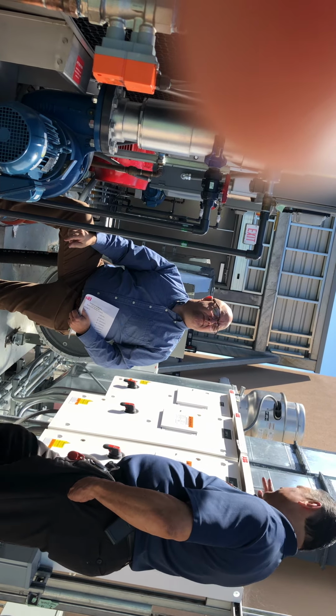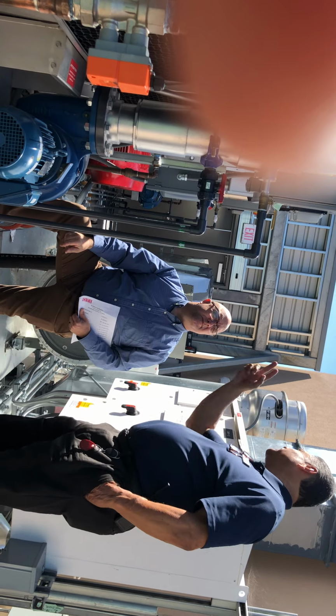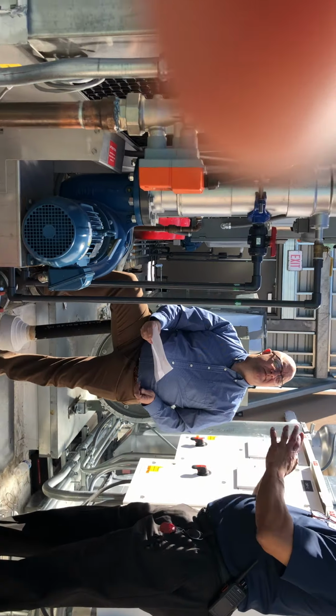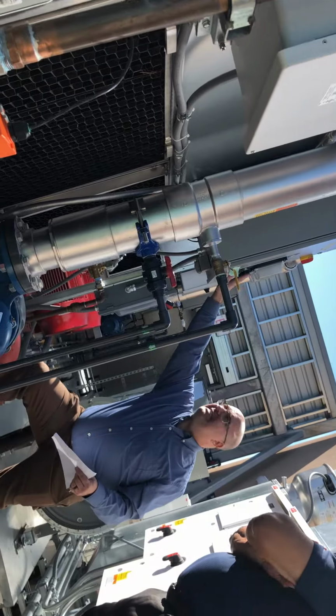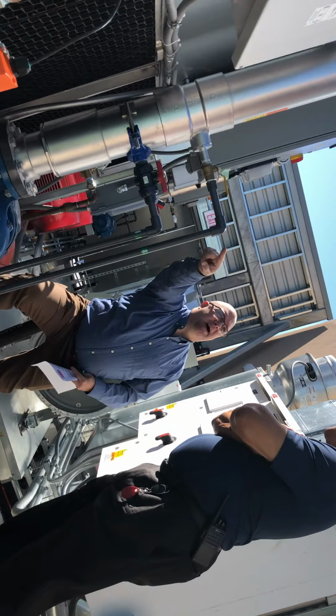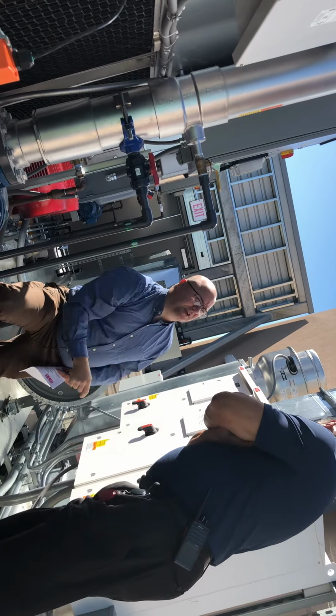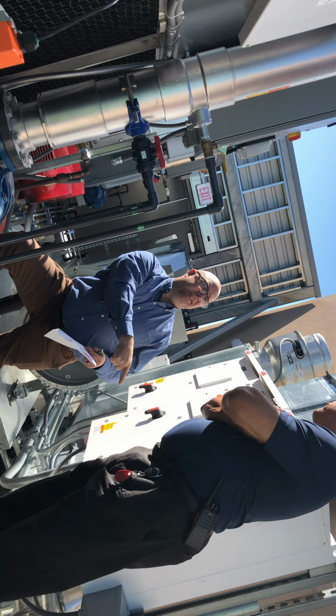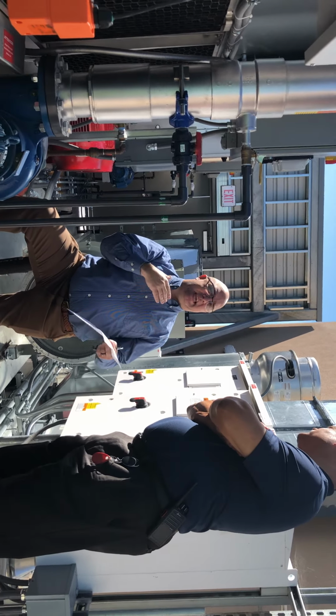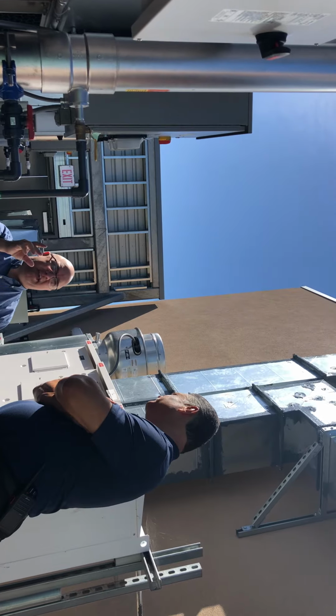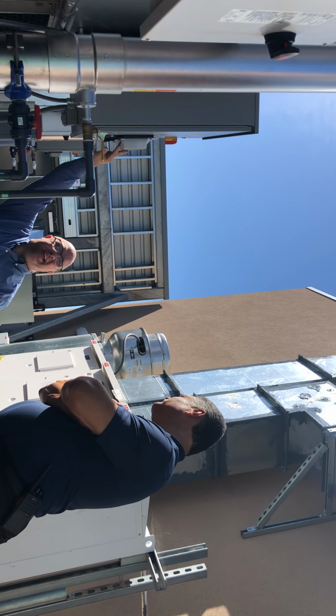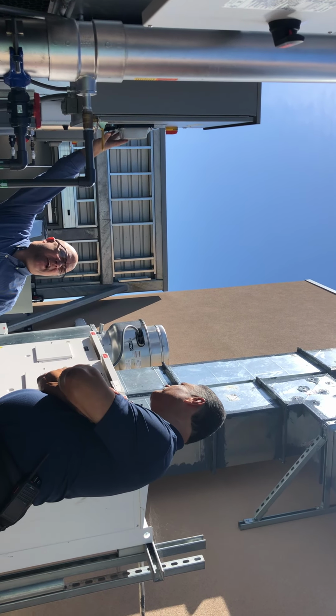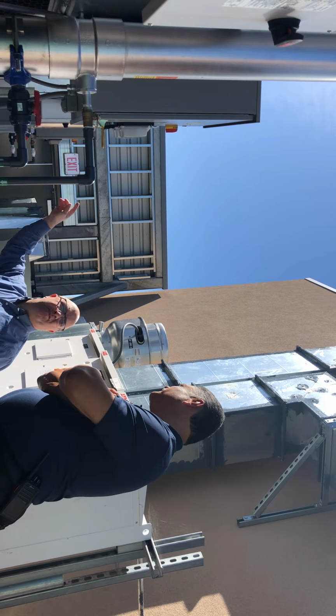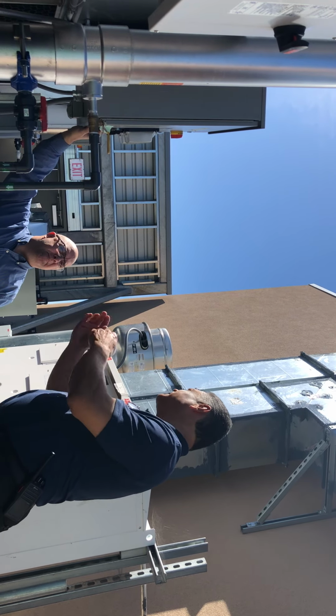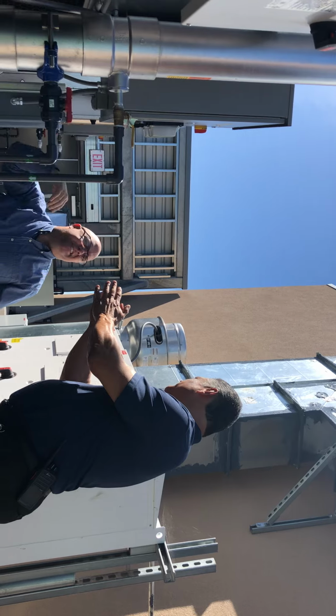Right. Question. Now, because you don't have to control those things right now, how does this know when to turn on? This is actually enabled by me, by my system, reading the temperature sensor below your feet. I can tell that the water's getting too warm, and I say, give me a cooling tower. Then I turn this on, and then it runs by itself. If I need more, I then turn on the second one, and it runs by itself. Technically, you have control. Well, just on and off.